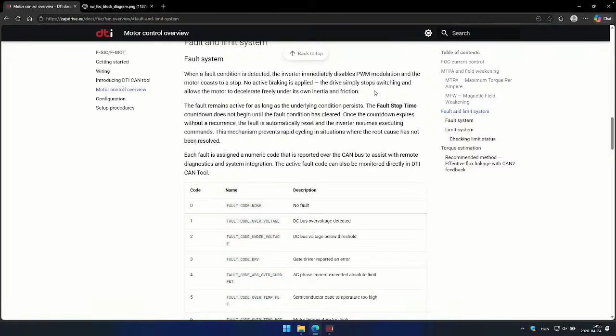The next one is the limiting and ramp control. We have a fault and limit system. The fault system helps to avoid damage in the system. So there are conditions like over voltage, under voltage, gate driver error, absolute overcurrent, and so on, when you have to stop the operation immediately because something critical happened, and you would like to stop and have the motor coasting, and restart the system when the condition is not active anymore.